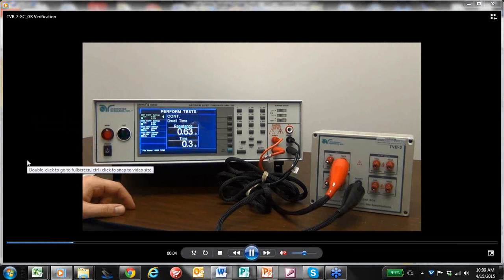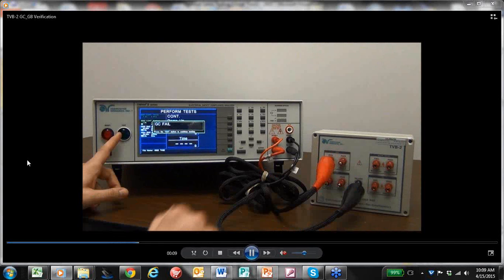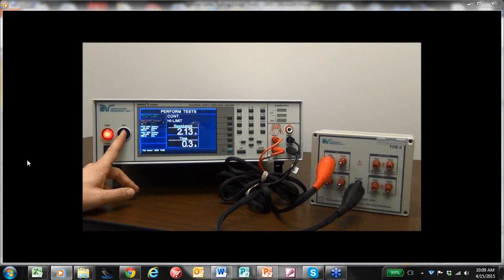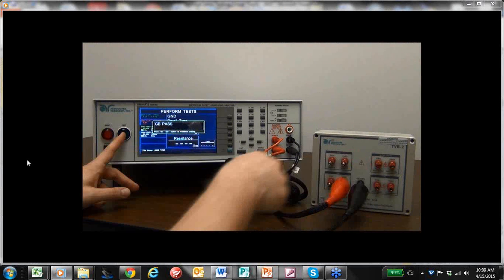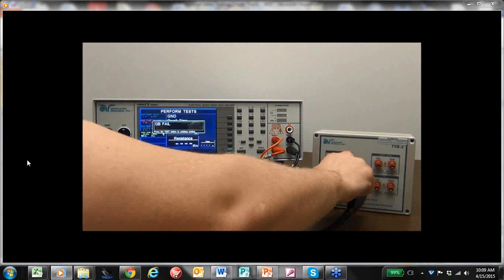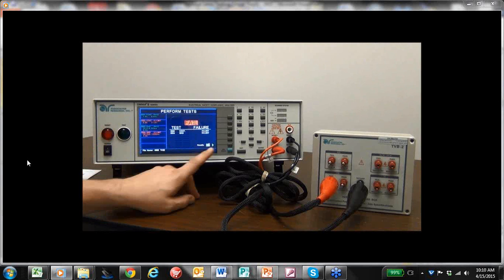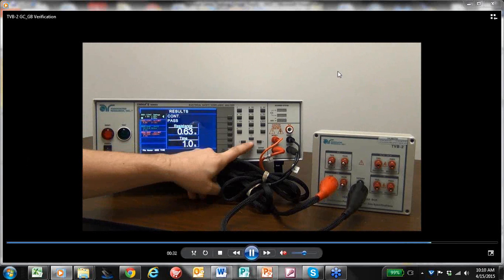In the video: a ground continuity pass is shown first, followed by a ground continuity fail due to exceeding the high limit. Next is a ground bond pass condition — the result is in milliohms. Finally, a ground bond fail is shown, where the resistance of the ground circuit exceeded the set threshold.